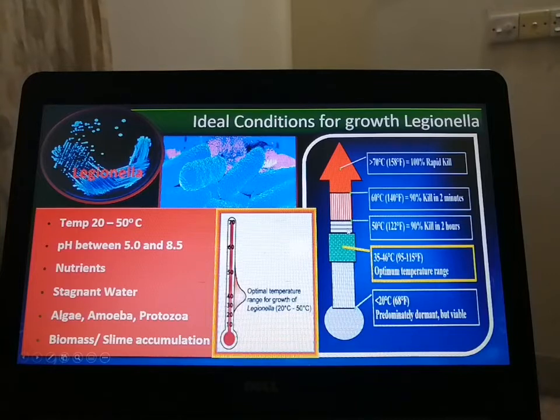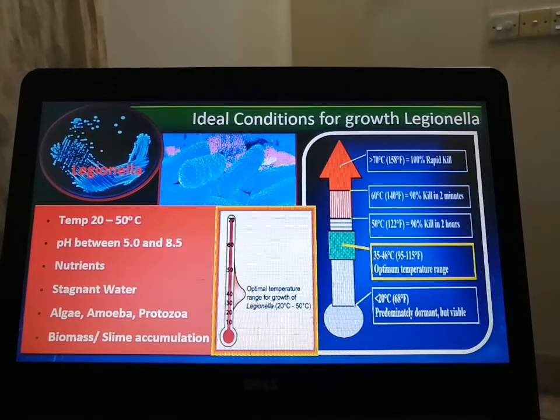But for cooling water systems that operate within a temperature range like 30 to 40 degrees, we can't apply this kind of high temperature water to sanitize. So we have to be very careful, because if the cooling system is fouled, under biofouling, has algae, or a turbid environment, and the cooling water is sprayed out as droplets mixed with air, inhaling that air always carries a chance of infection by Legionella bacteria.